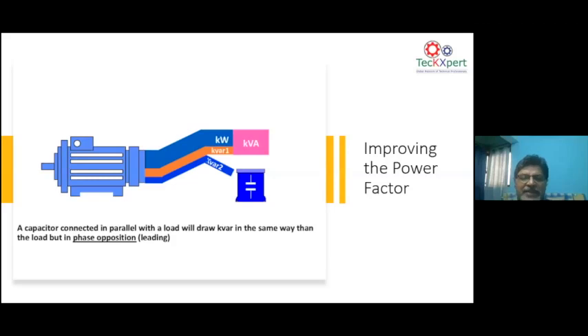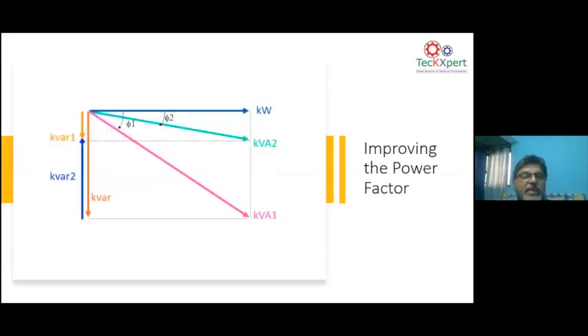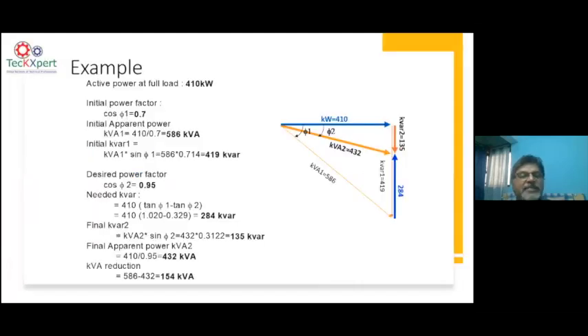So in the process, the exchange of energy takes place between the magnetic field and the electric field of a capacitor. That is how we improve the power factor. As we see in the simple exercise, if you have a load of 410 kilowatt, let's say at a power factor of 0.7, now as the power factor is improved by a capacitor bank to 0.95 from 0.7, you will see that the kVA is reduced by about 154 kVA.